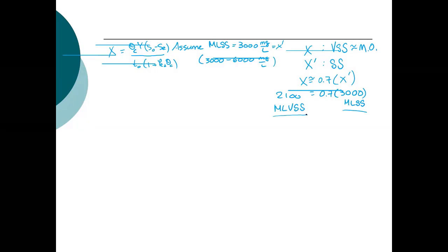And if we substitute into this equation here, 2100 is equal to the 8.2 that we calculated. Y is the yield coefficient that was given as 0.6. 84 milligrams per liter is the soluble BOD entering.